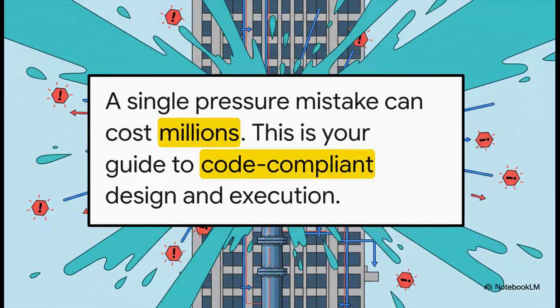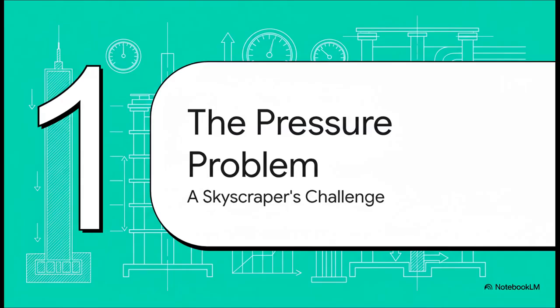One single mistake in your pressure calculations can lead to a total system failure. We're talking massive floods and repairs that can run into the millions of dollars. We're going to walk you through the roadmap to make sure that never ever happens on a project you're a part of. Okay, first things first. We have to wrap our heads around the real enemy here. And surprisingly, it's not the chillers, it's not the pumps. It's the simple but immense, crushing force of pressure that's created by the building's own height.